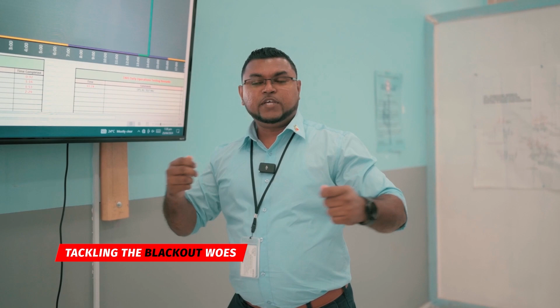Let's talk about taking feeders off. We don't randomly take off feeders, right? We developed an algorithm that would determine which feeders to possibly take off. Now, this is done based on criteria such as when last the feeder was out, how long it was out. Was it out for planned maintenance? Was it out because of an emergency maintenance? Was it out because of generation shortfall? So we do a rotational system. So we don't give the same place blackout twice in the same day, unless it is absolutely necessary. Right.